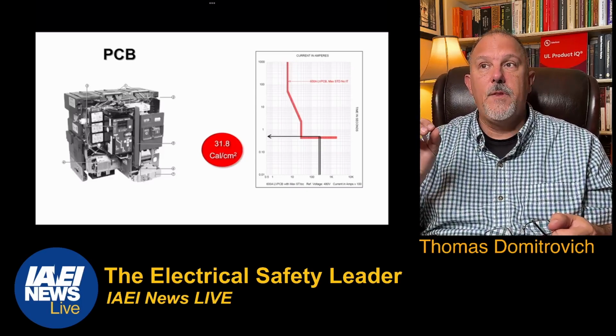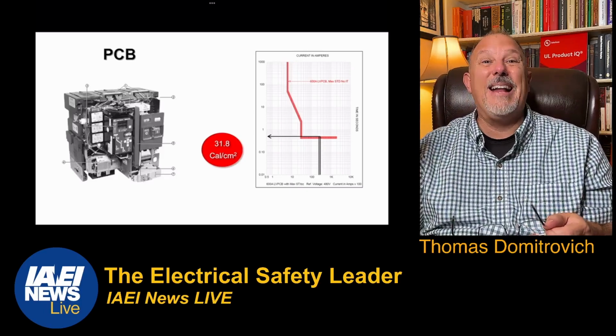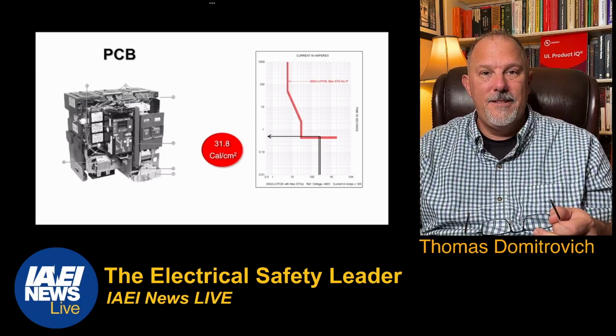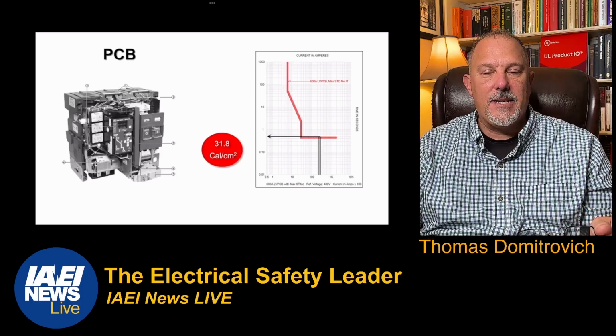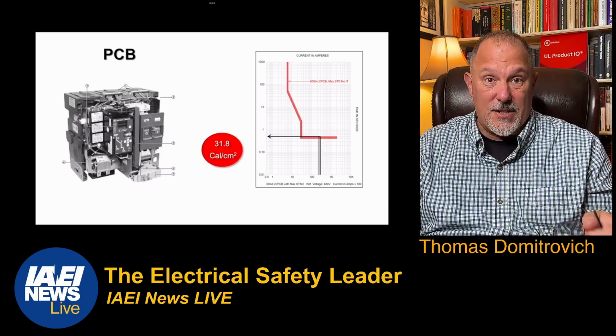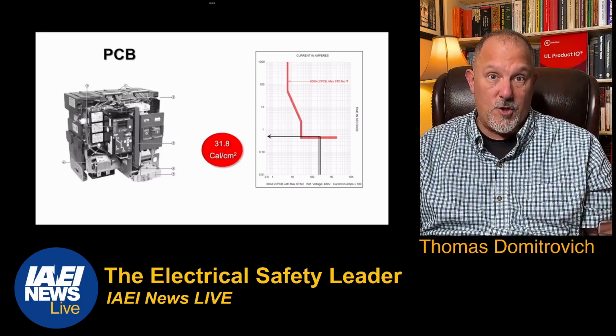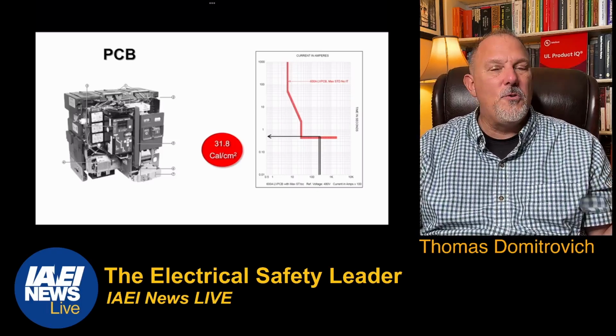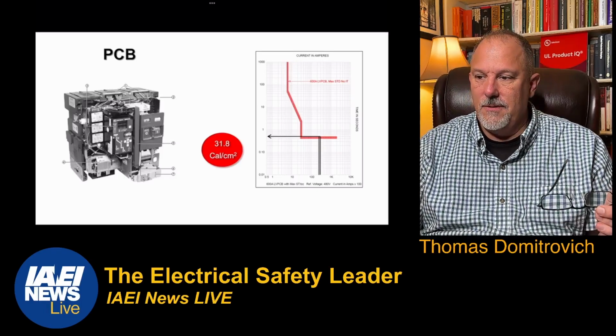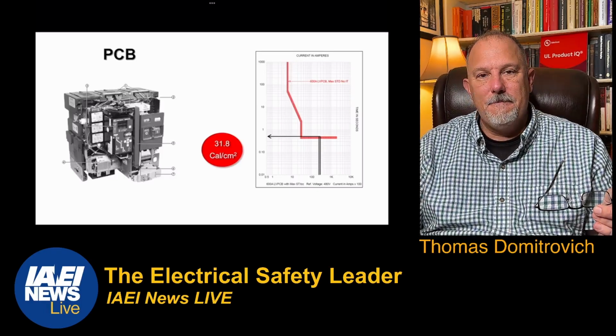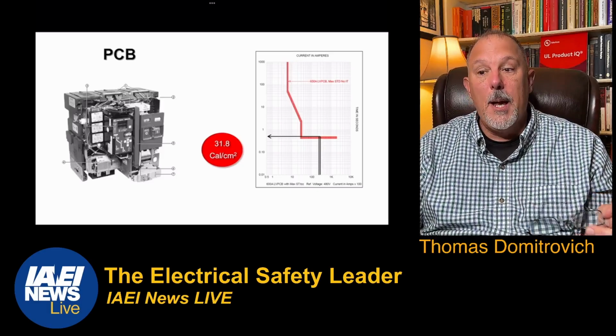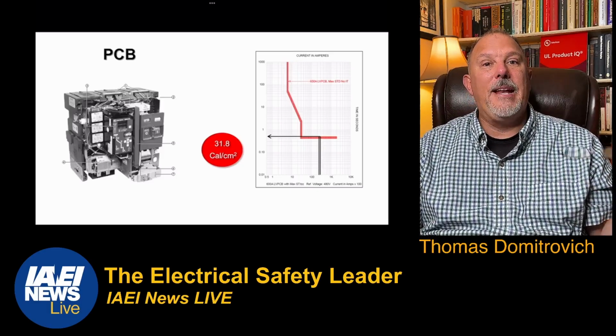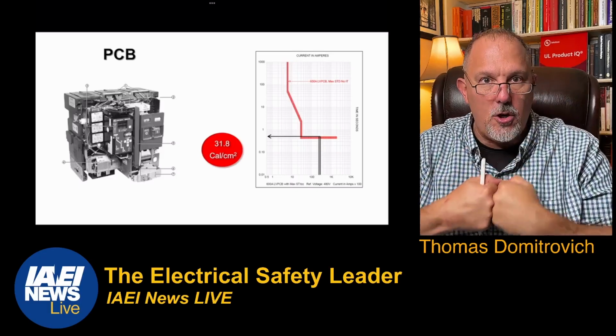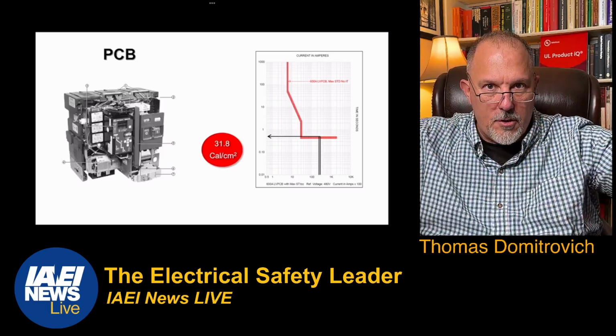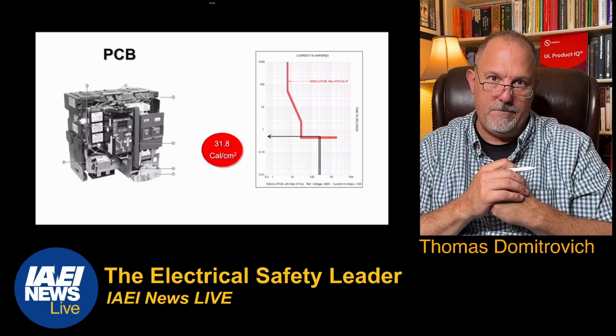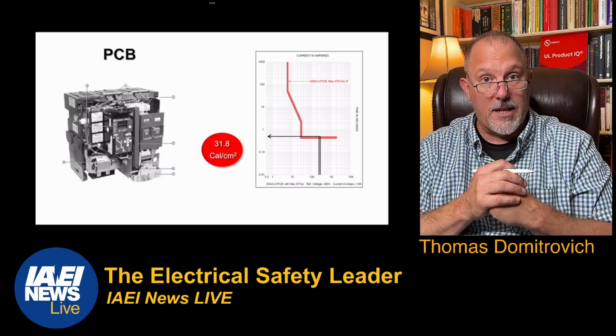The instantaneous value is at the interrupting rating. So if this is 65,000 amps, I can say the instantaneous can be set to 65,000 amps on some of these breakers, depending upon which one you bought. And I can hold those contacts closed for 30 cycles. And that is still a 600 amp breaker, but it's bigger, it's beefier, and it's holding those contacts closed longer so that all those little brothers and sisters downstream can do their job and isolate the faults for selective coordination.